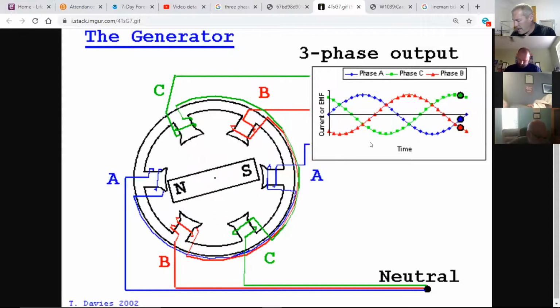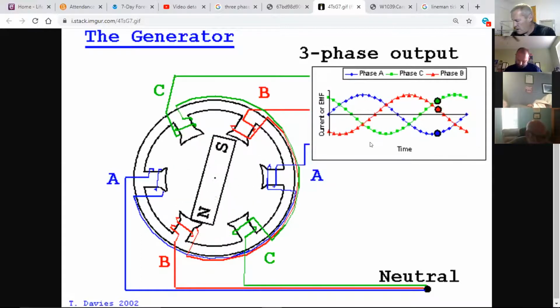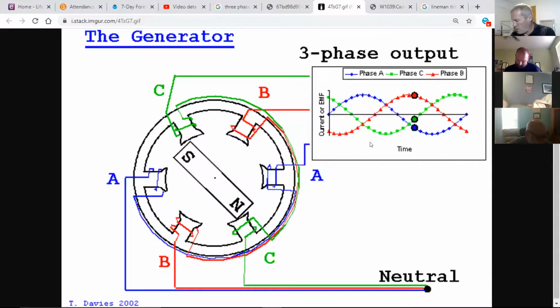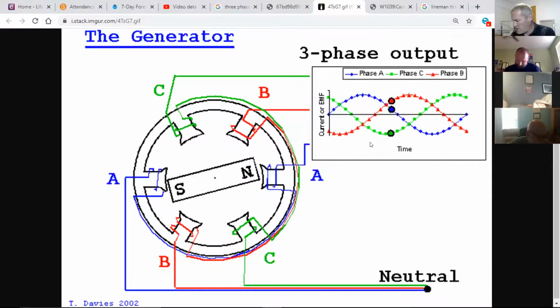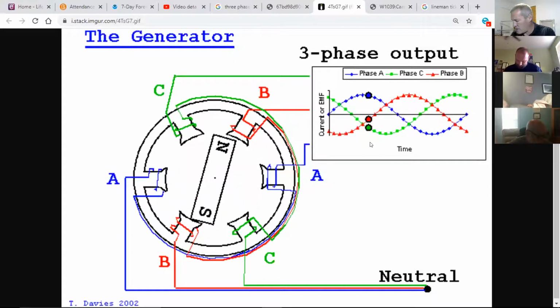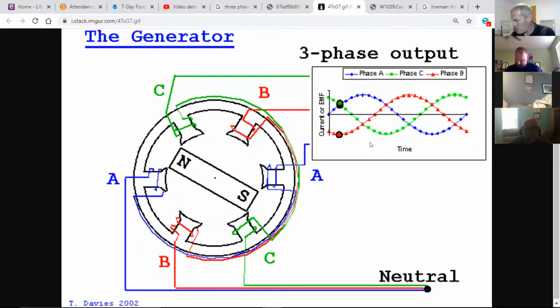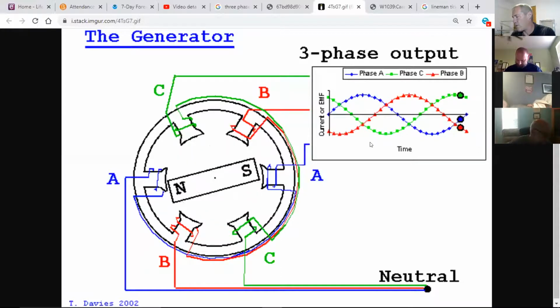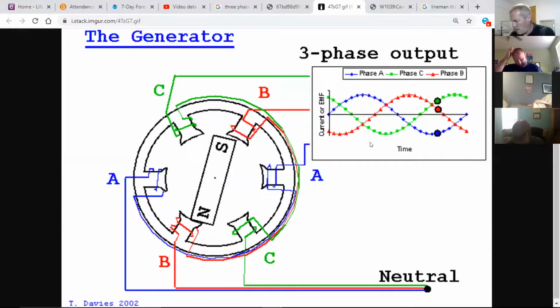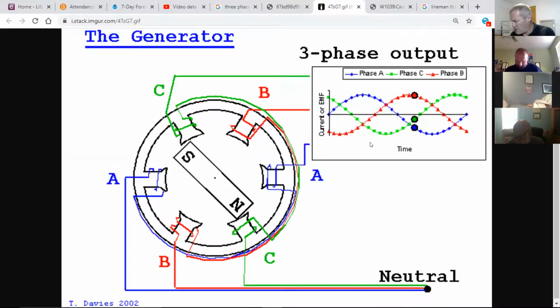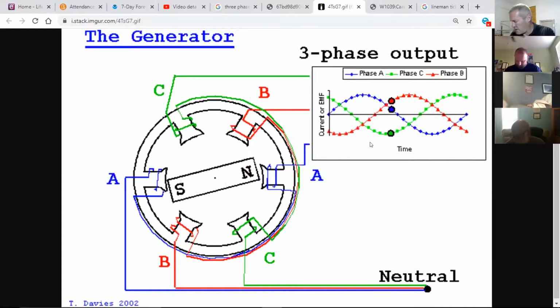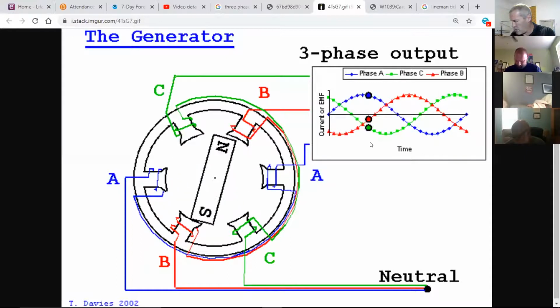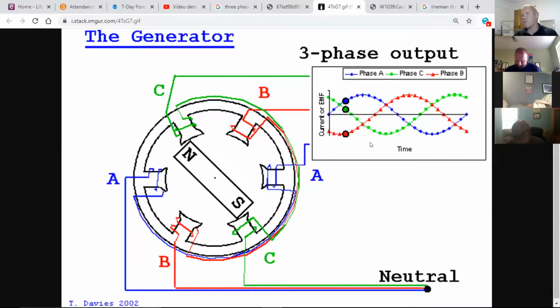Number three: in a balanced three-phase system, the conductors need be only about 75% of the size of the conductors for a single-phase two-wire system. When they say two-wire, that's a primary and a neutral of the same kVA rating. This helps offset the cost of supplying the third conductor required in three-phase systems.